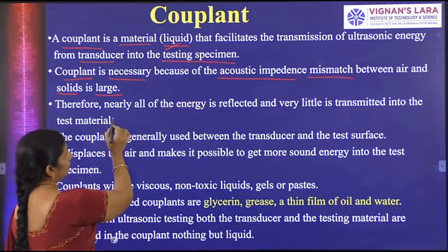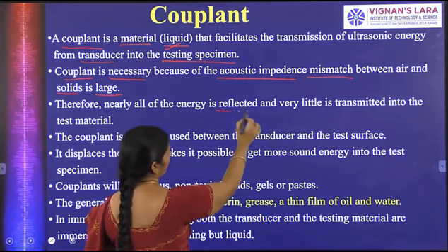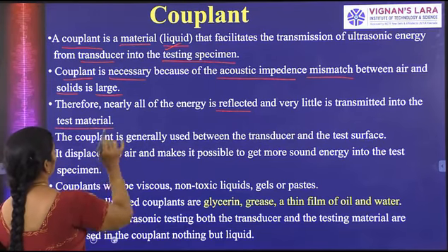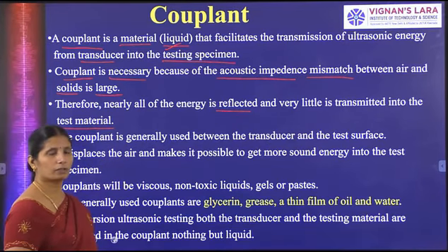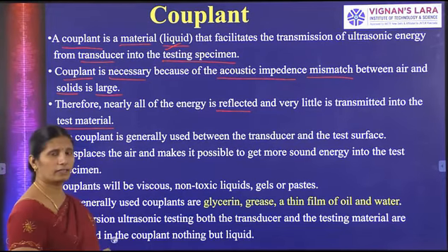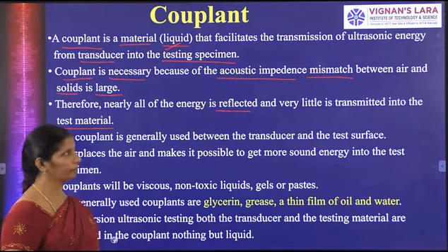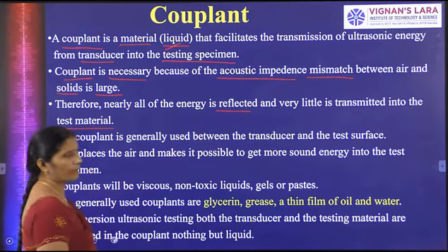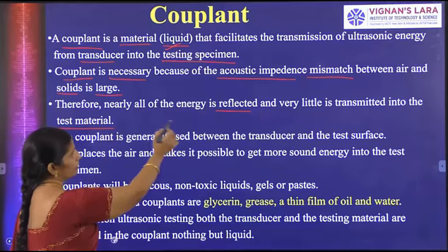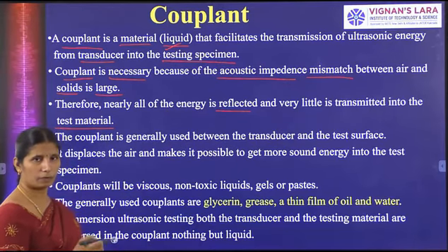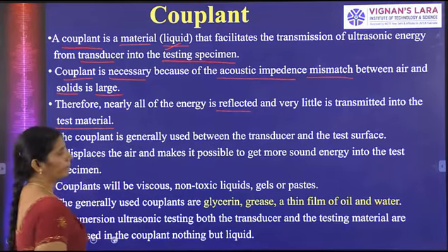So nearly all the energy is reflected and very little energy is transmitted into the testing material. If there is no couplant, then most of the ultrasonic energy is reflected back. It does not enter the testing specimen. Due to the acoustic impedance mismatch, all of the energy is reflected back and only a very small amount of ultrasonic energy is transmitted through the testing material.